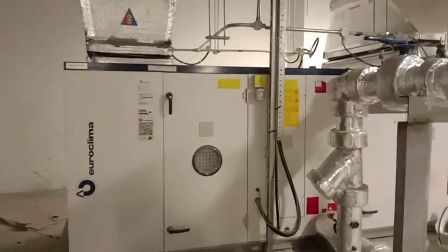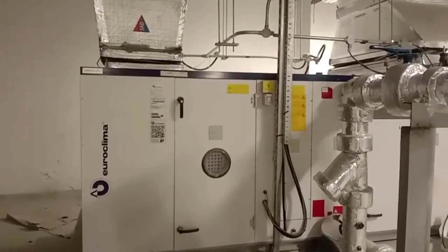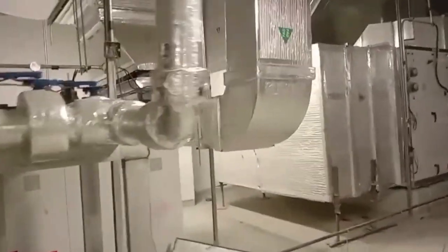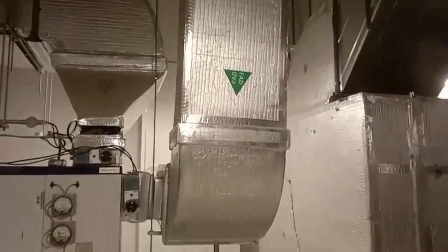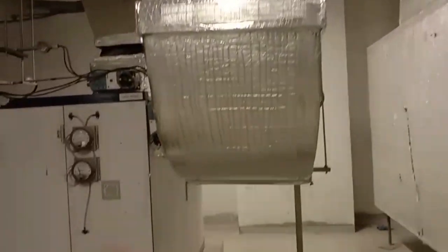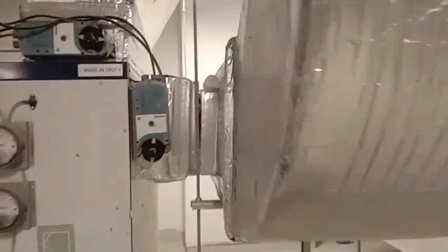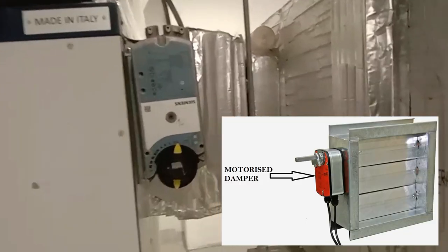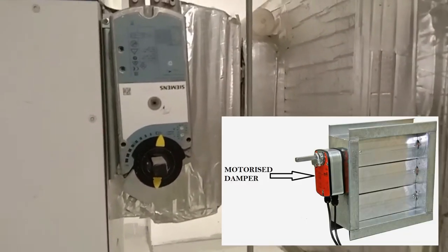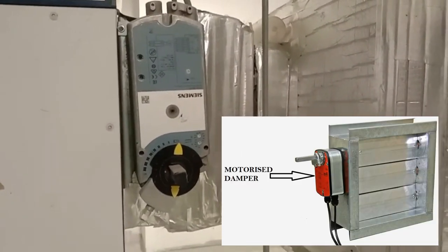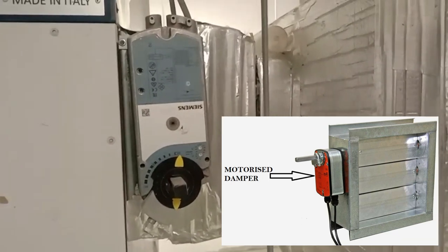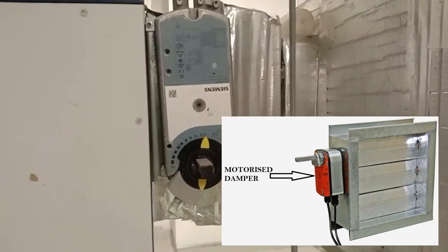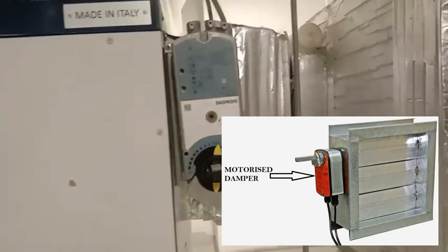At the same time, we've done the duct works as well. So as you can see, I'll start first with the fresh air duct. On this side, you can see we have the fresh air duct, which is leaving from outside, collecting air from outside and then bringing it inside the AHU. At this portion, we have a motorized damper. This is a motorized damper, which is used to open and close the damper. So it stands there as a door, which permits the air to move inside the AHU.